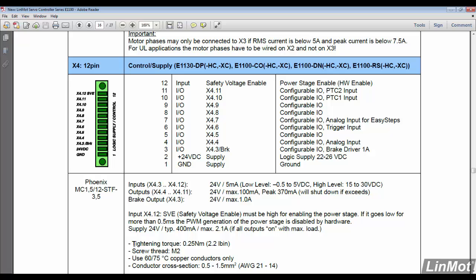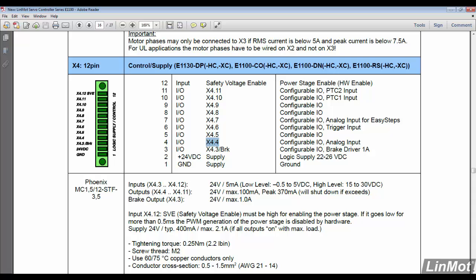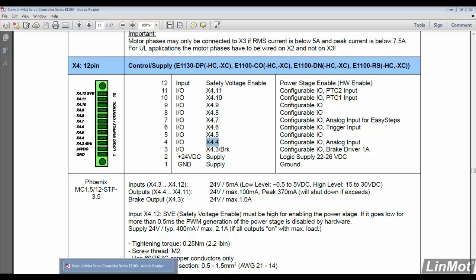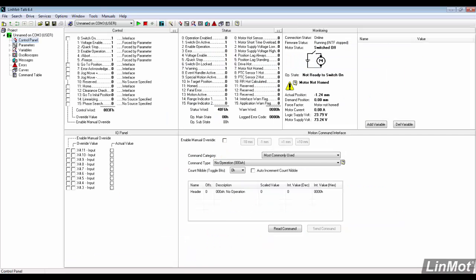In the drive's installation guide, we see that X4.4 is a pin needed for the analog input. The signal conditioning module will be wired to ground and X4.4. Once everything is physically connected, we can set up the load cell in LinMot Talk.